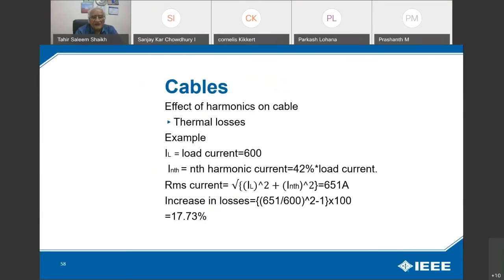Now, you can see in this example, the harmonic current increased by 42% and the losses increased to 17.73%. That's why the thermal losses increase in the cable. Sometimes the cable bursts. I have seen that, even in very big plants. I have seen the bursting of the cables.